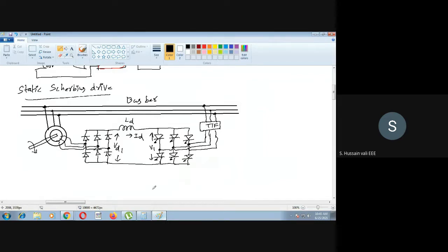I will show you here. See this once again, same thing. You give the power to the stator. This is the stator. Then the rotor does some work. Other than that, the remaining is S into P_ag, that is the air gap power, that is slip power. This slip power you tap here and send to this three-phase bridge rectifier. The rectifier converts this AC to DC. Then that DC is connected to, now what is this once again? You can call this an inverter right now.